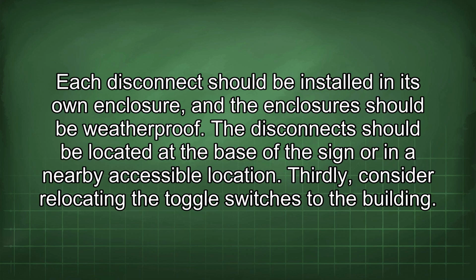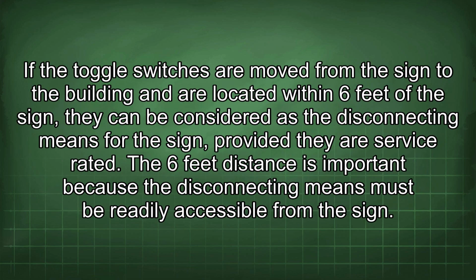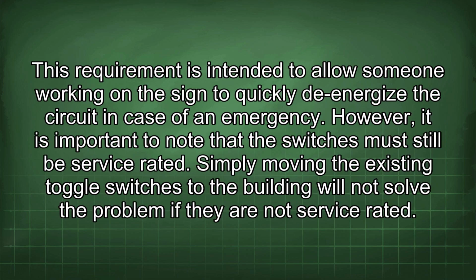Thirdly, consider relocating the toggle switches to the building. If the toggle switches are moved from the sign to the building and are located within 6 feet of the sign, they can be considered as the disconnecting means for the sign, provided they are service rated. The 6 feet distance is important because the disconnecting means must be readily accessible from the sign. This requirement is intended to allow someone working on the sign to quickly de-energize a circuit in case of an emergency.